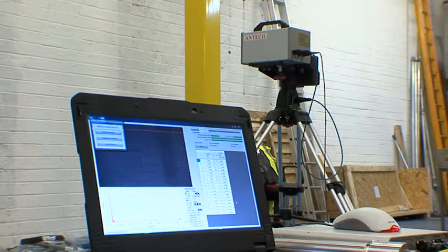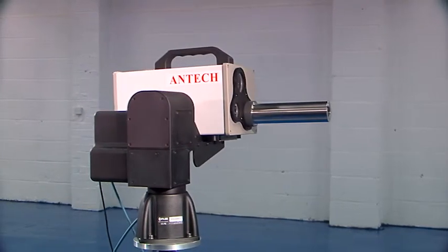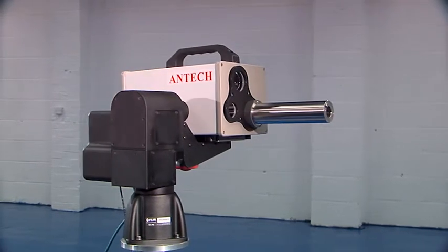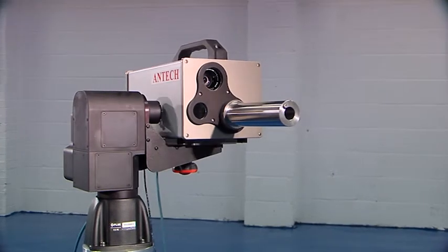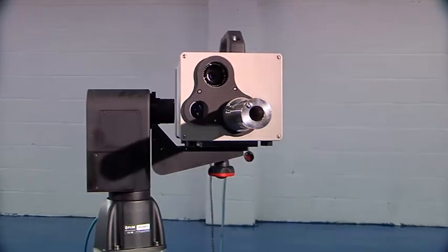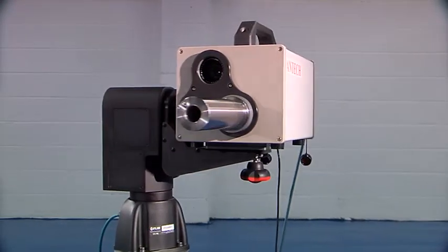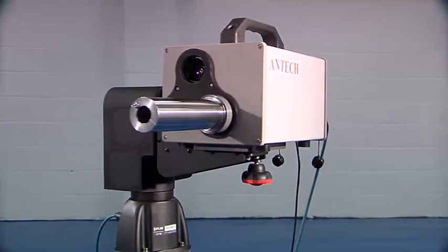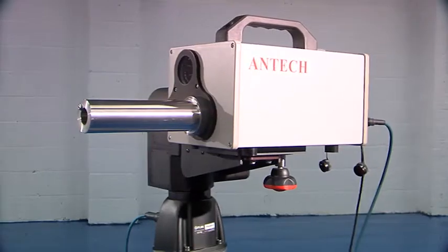RadSearch has several advantages compared to other gamma cameras. These include improved energy resolution of 2.5% based on the use of a 1-inch lanthanum bromide scintillation detector, and high detection efficiency, measuring down to 3 nanosieverts per hour. As well as the ability to identify over 50 radionuclides, it is also the only device of its kind able to measure and quantify radioactivity in terms of becquerels or curies.